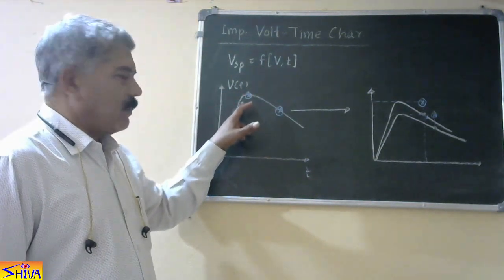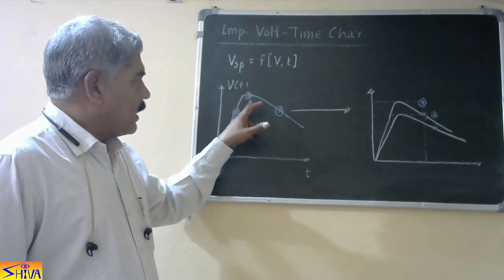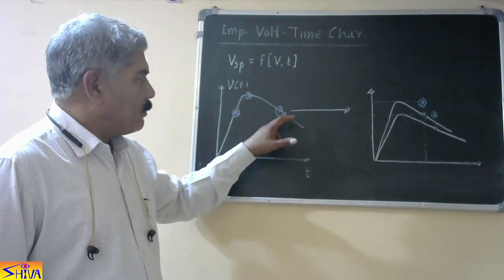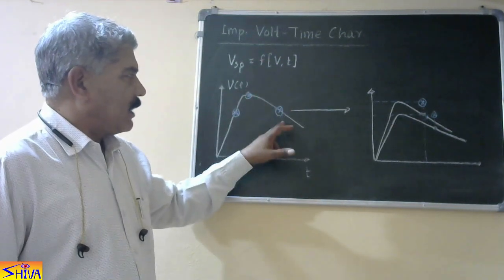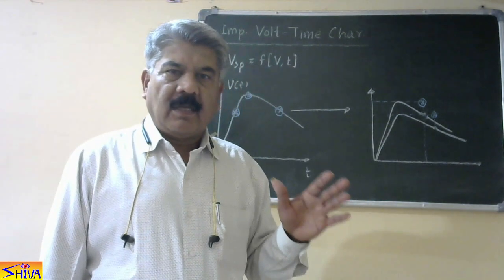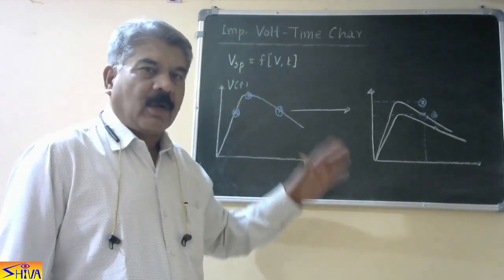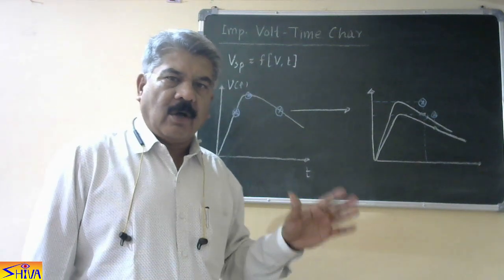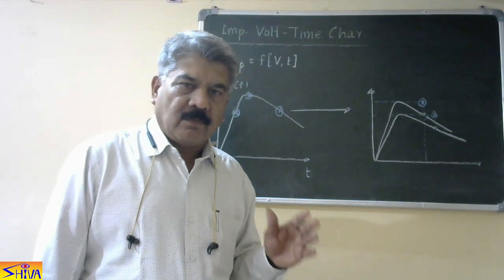If spark over takes place, there are three possibilities. Number one: spark over occurs on the wave front, that is on the rising portion. Second: spark over occurs at the peak value. Third: spark over occurs at the wave tail, that is at the decreasing portion of the impulse wave. We apply a series of standard impulse voltage waves, find a number of points, and then join all these points by a smooth curve — that will be the impulse volt-time characteristic.